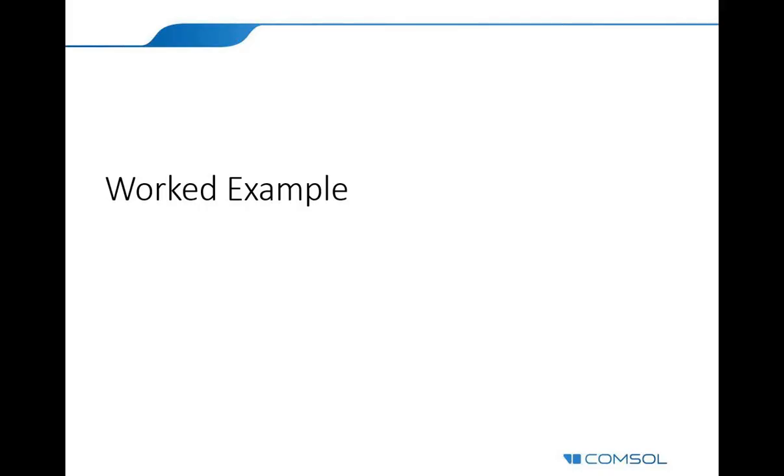Copy of the presentation, I commented about that. I will talk about the hyper versus cryo. I'm going to have an example of that. And then the question also says, for RF ablation, can you set up an electric resistivity function? And absolutely, it is very typical that it is a temperature-dependent resistivity.